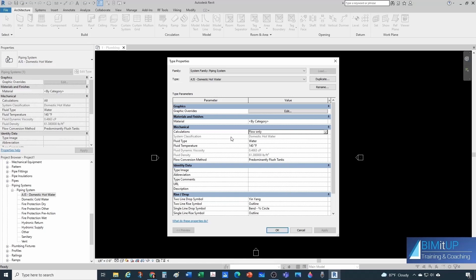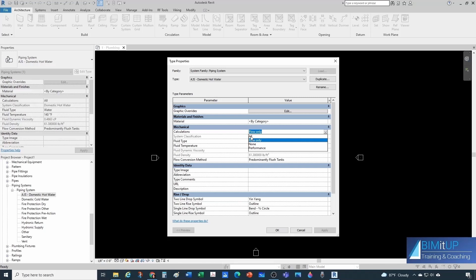You have your Fluid Type — in this case it's water — and you can create different fluid types. You specify your temperature here because fluid type and fluid temperature determine the viscosity of the fluid. These two parameters fix the viscosity, which in turn determines your pressure drop in your pipes. But again, if you're not calculating performance, this doesn't matter too much.